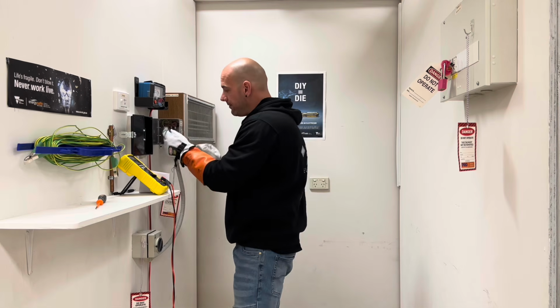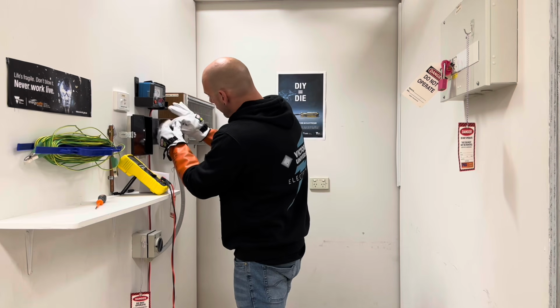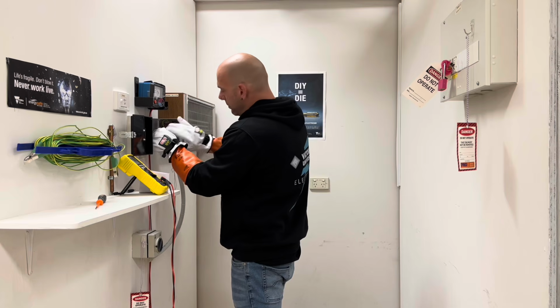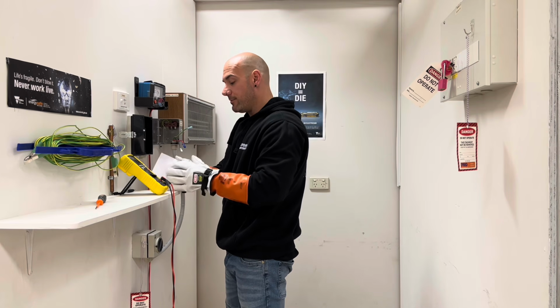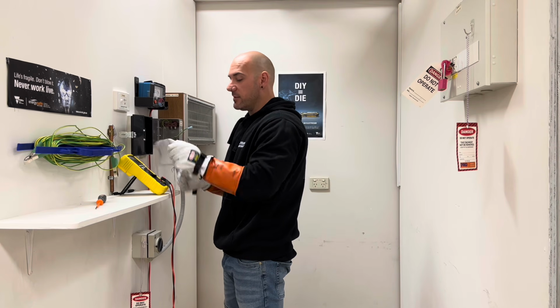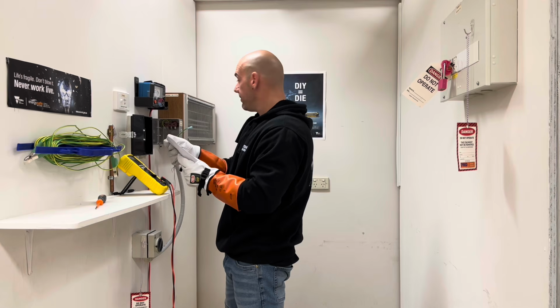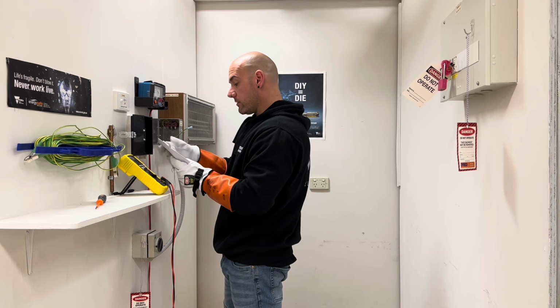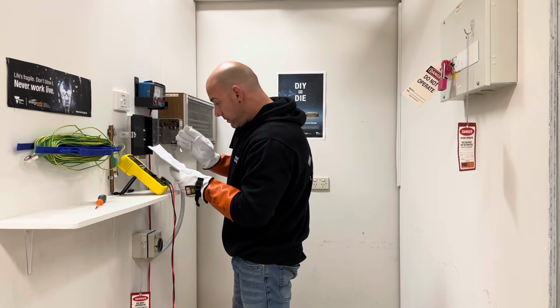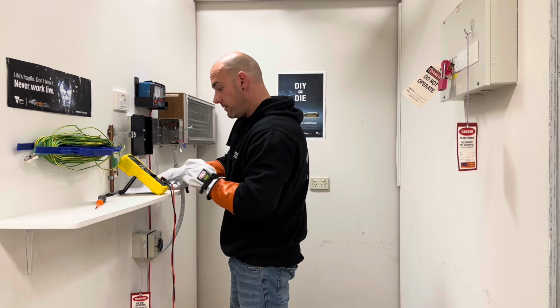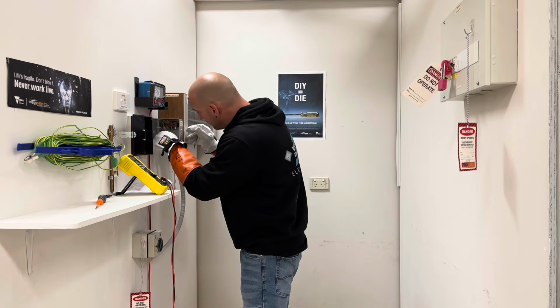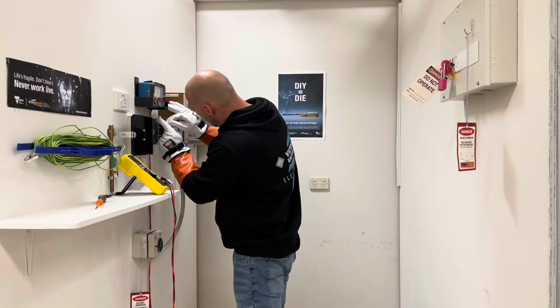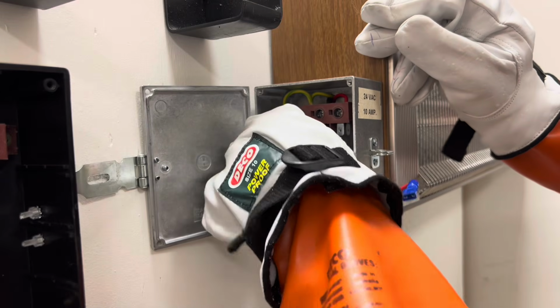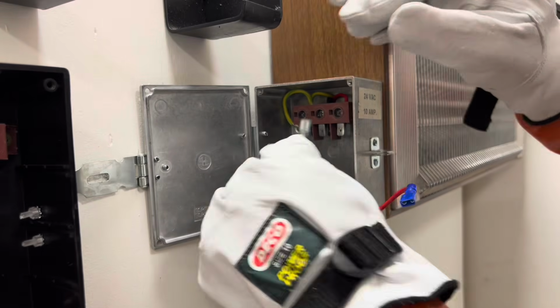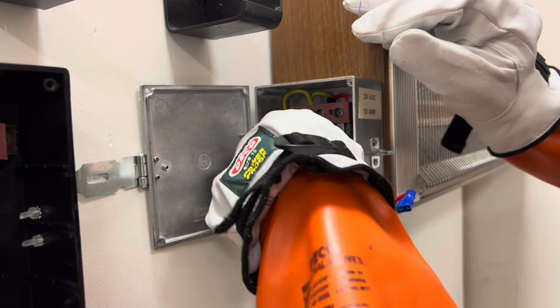Screw the conduit on, and we connect our earth first. But we need to make sure that the heater is the same and the terminal block is the same. So the heater details are all the same, and the terminal block, earth, neutral, active. Okay, so earth conductor on first, neutral, and active.